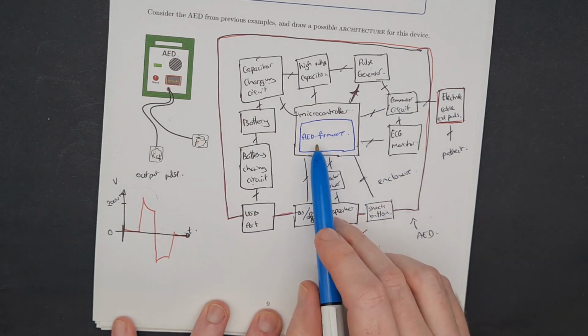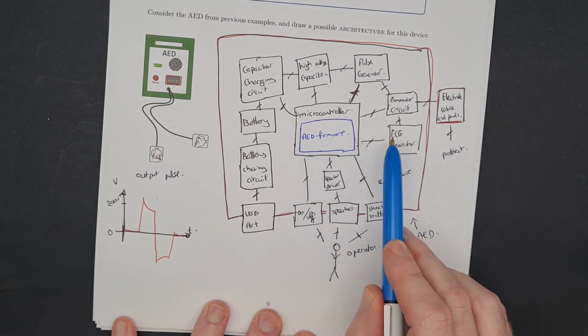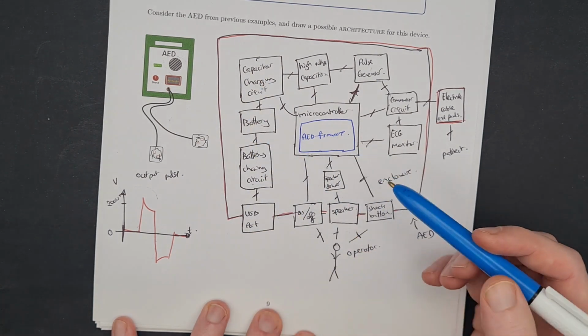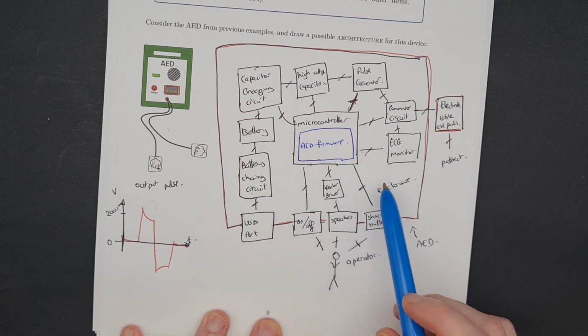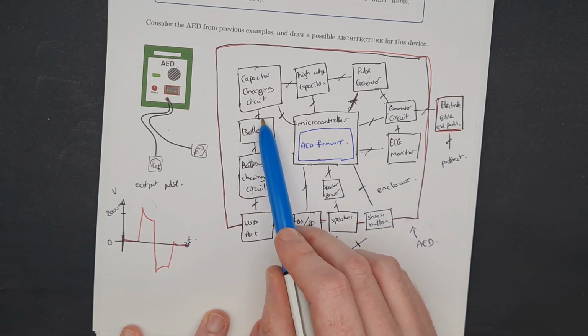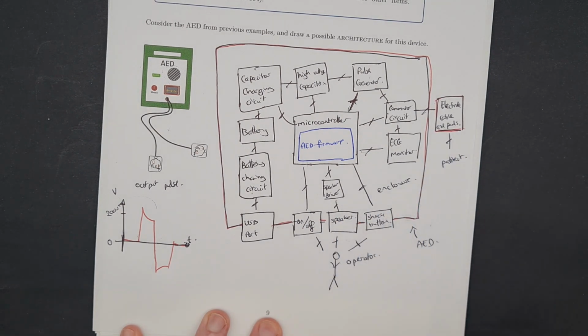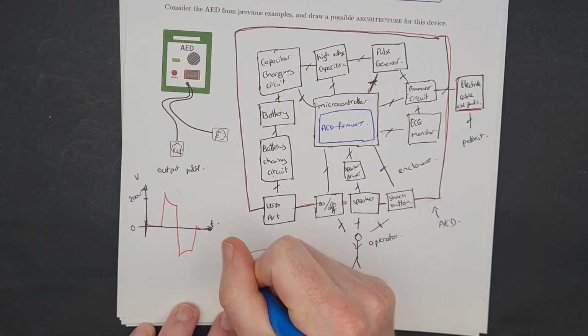But the firmware and software in general we will treat a bit differently because in firmware, we will try to test every item we decompose it into. But in hardware, generally you don't, but there's always exceptions. You might end up having a few tests on just the battery itself in something like this, but most tests you'll do from looking at the AED as a kind of box of its inputs and its outputs effectively.